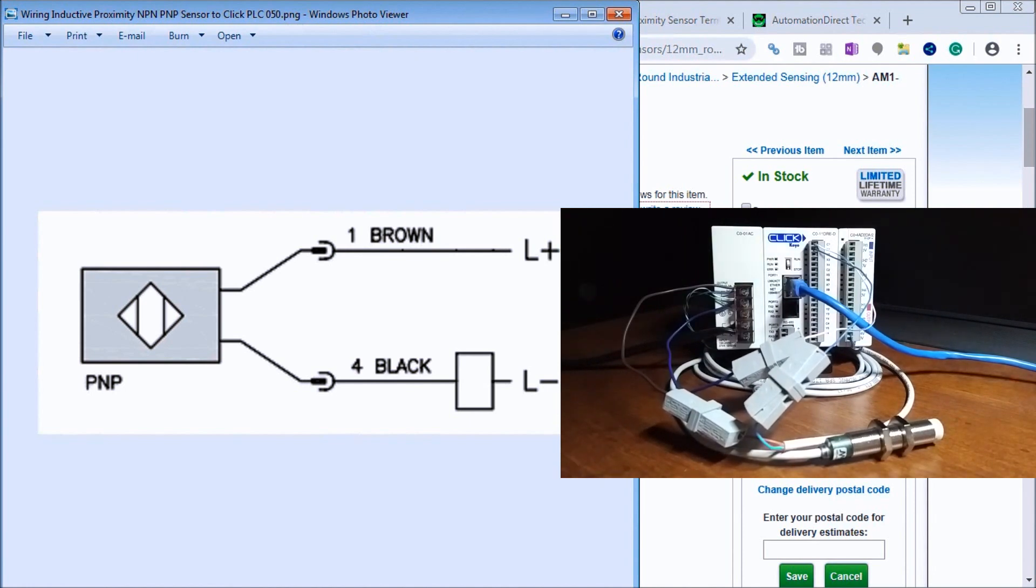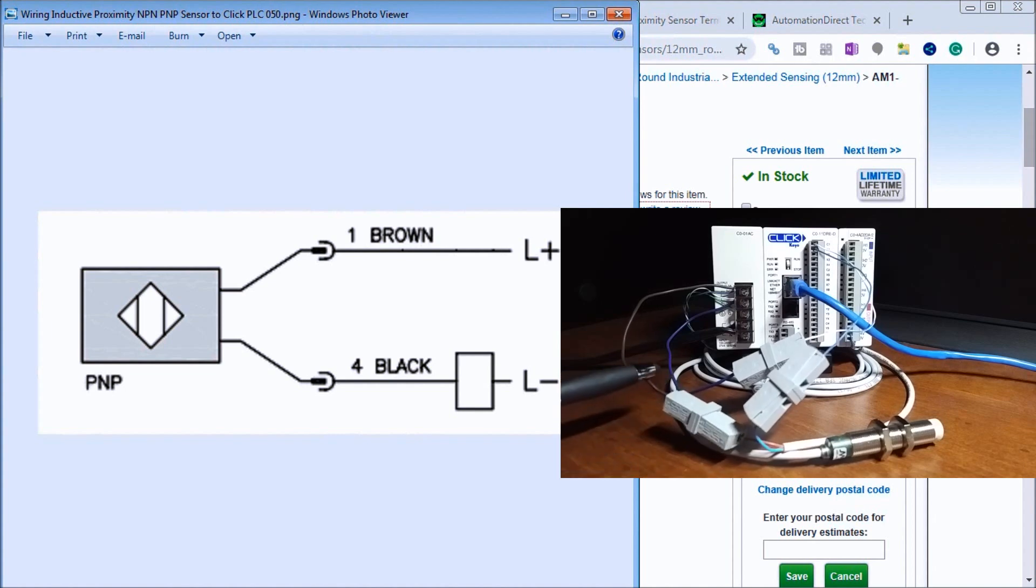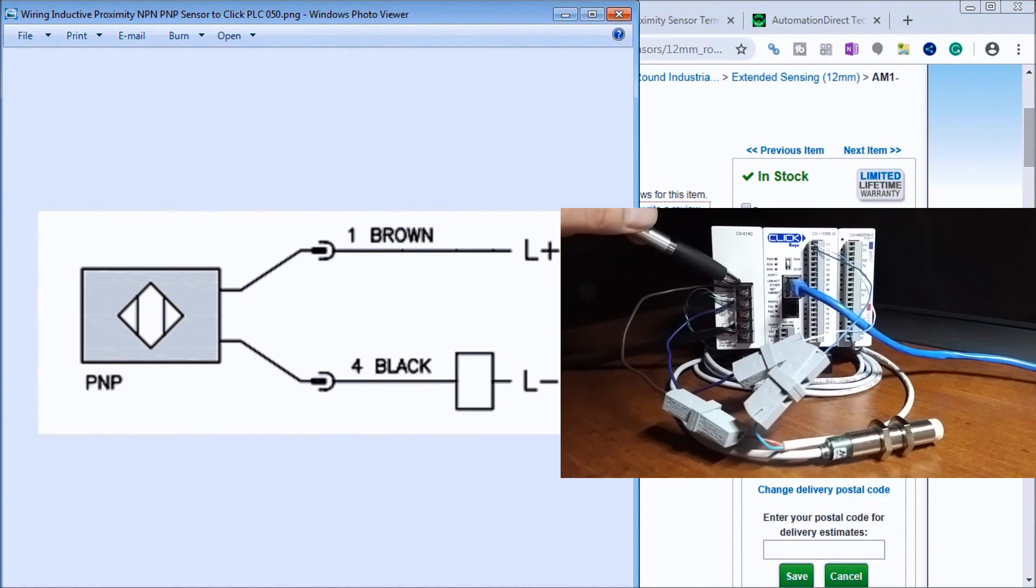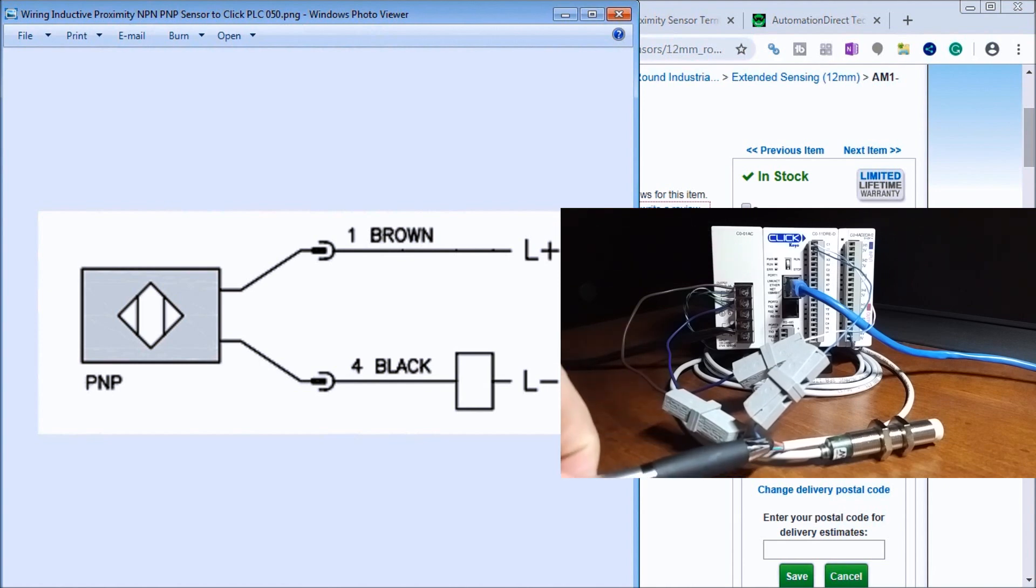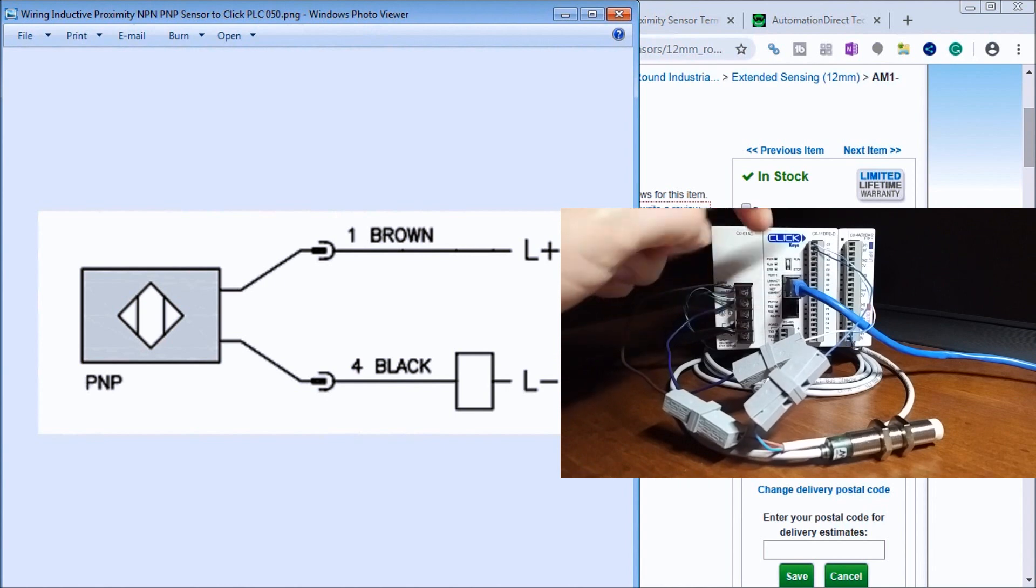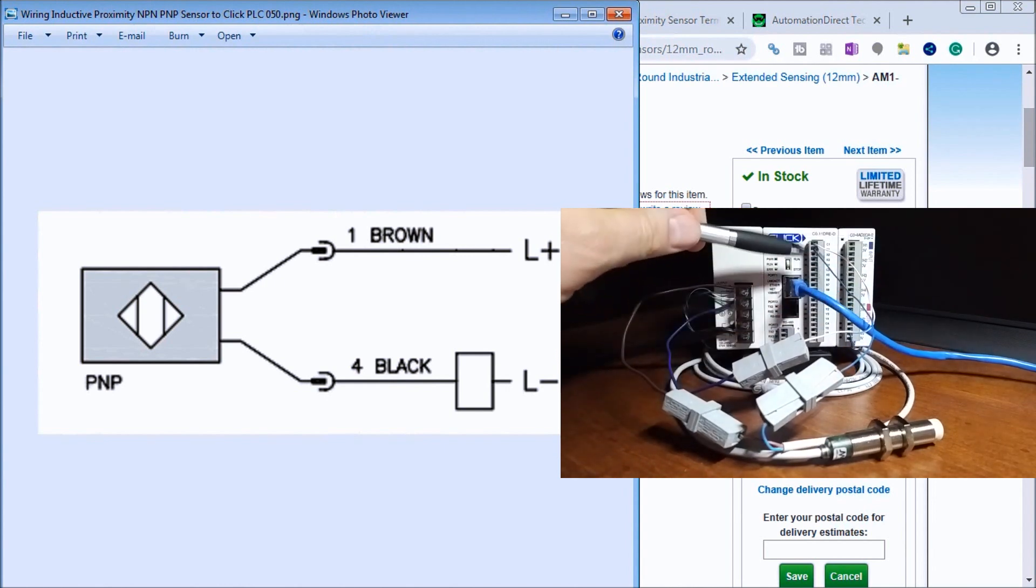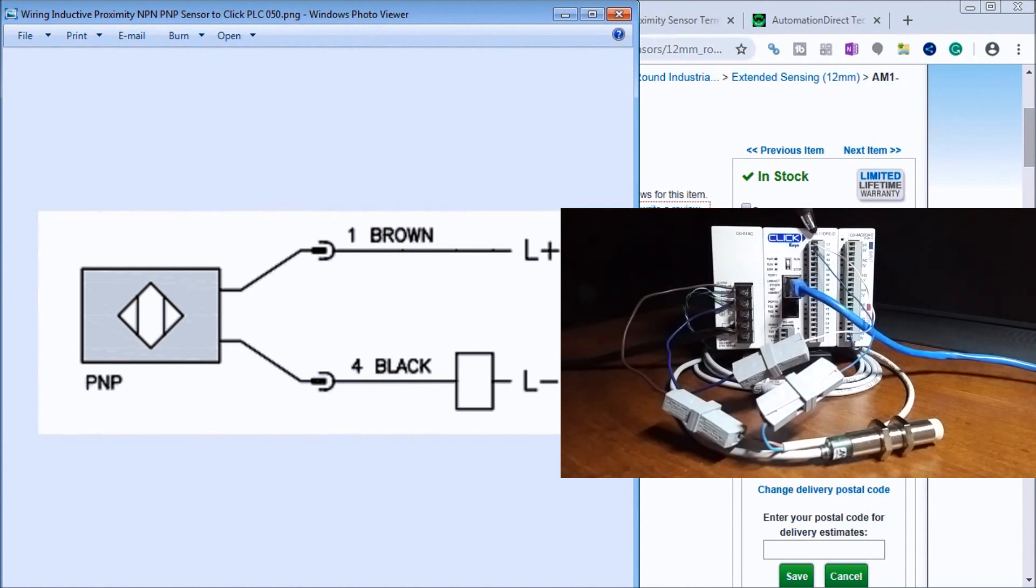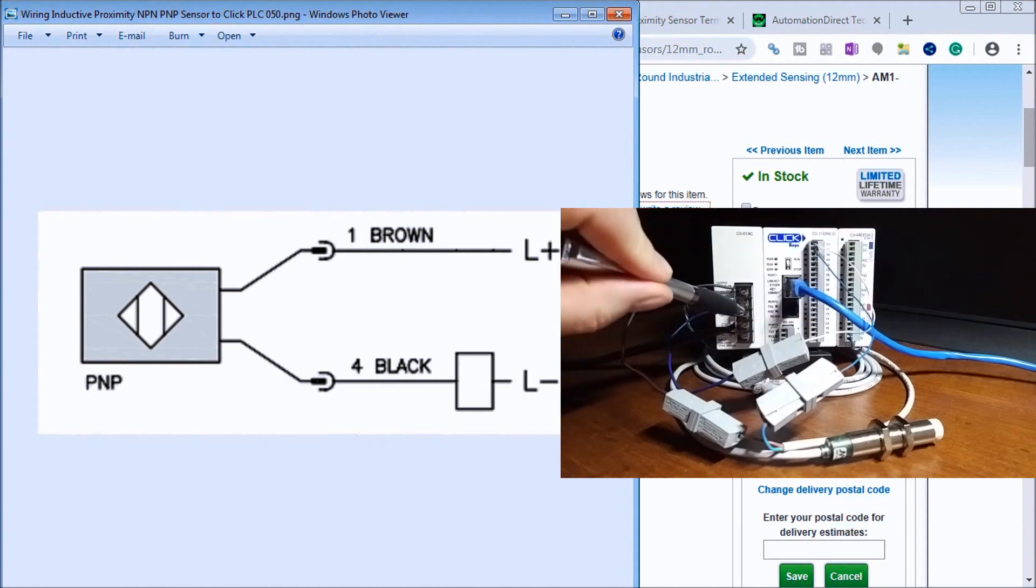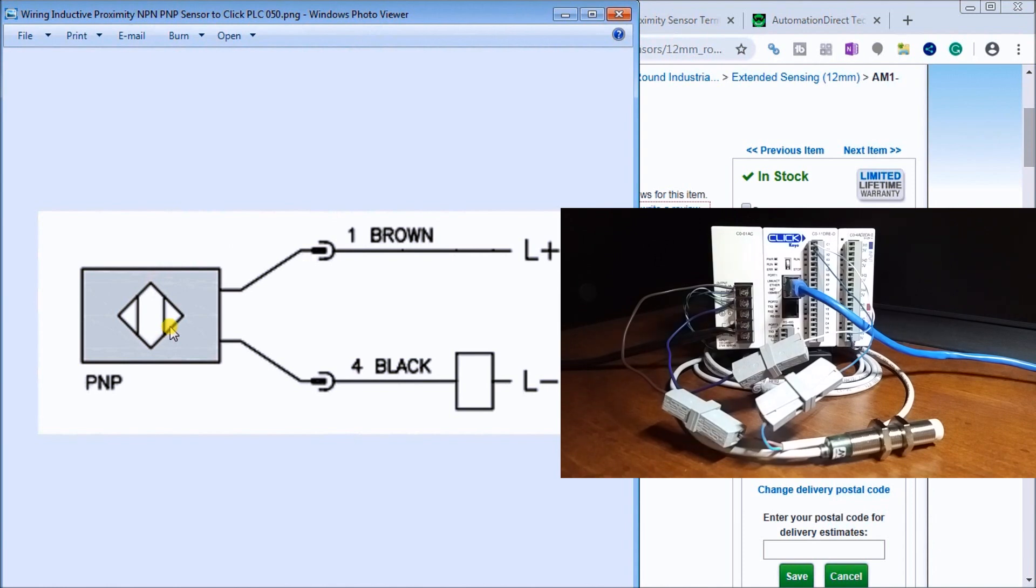Quick review: we've got our brown wire now connected to the brown wire going back to our plus voltage. Our black wire from our sensor is going to our input, and our common for our input is going back to our zero volts. Now we have it wired up as PNP or positive switching or sourcing a load. Let's plug that PLC back in now.